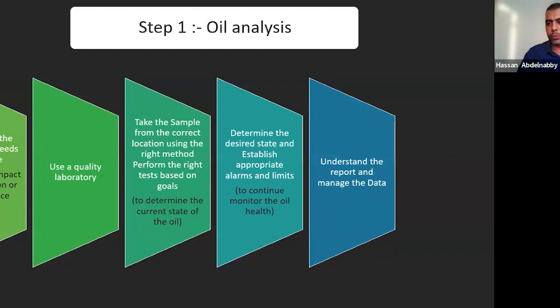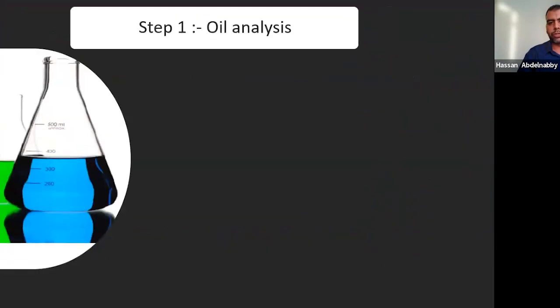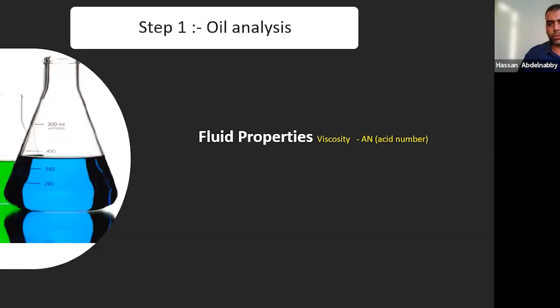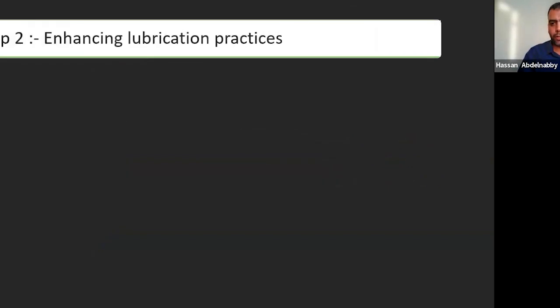Your side of the problem is to understand the report and manage the data properly to come up with corrective actions to preserve your oil health. The oil sampling and test must cover fluid properties like viscosity and acid number, as well as contamination indicators like particle count and moisture content. In severe cases, ask for ferrographic particle analysis and analytical ferrography to find the root cause.